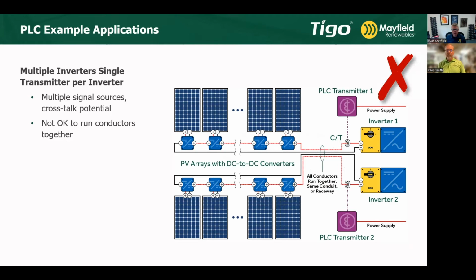Where you run into problems is if you try to run the conductors together. You have cable trays on the roof, or EMT, or conductors inside a pipe - even if array 1 and array 2 are separated by a walkway, it's a lot easier to bring them to a single point, run a single pipe back to where the inverters are, and then branch them out again. That's where you're going to come into problems.